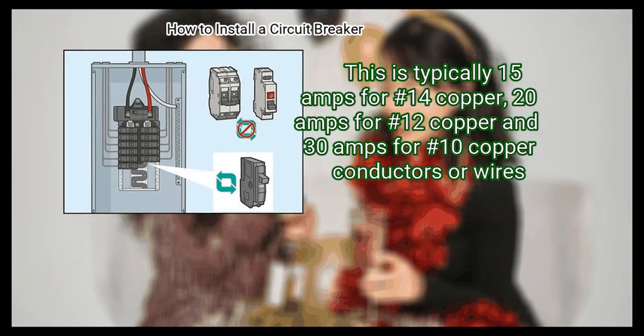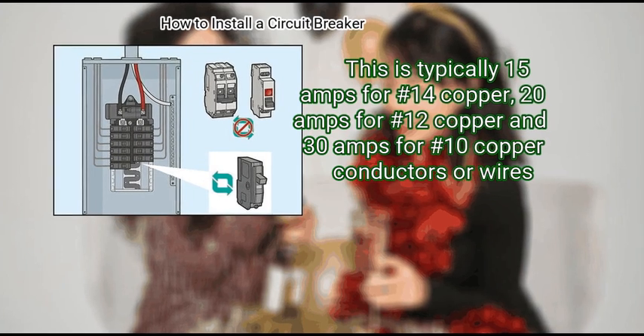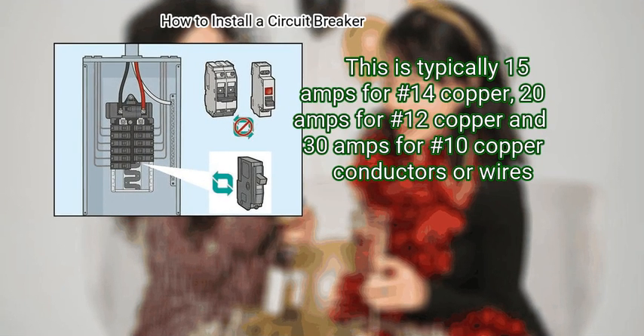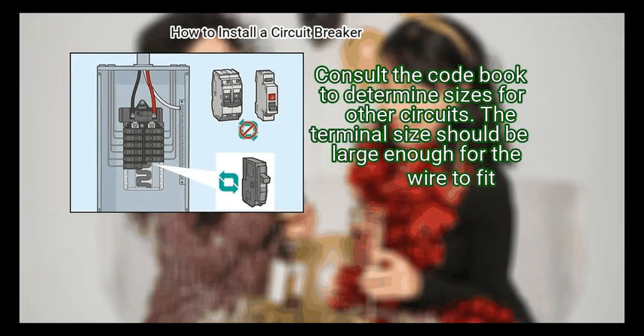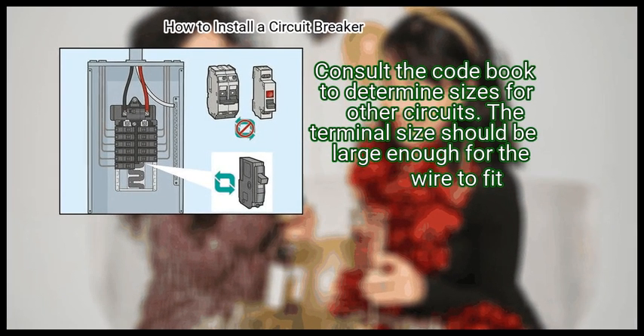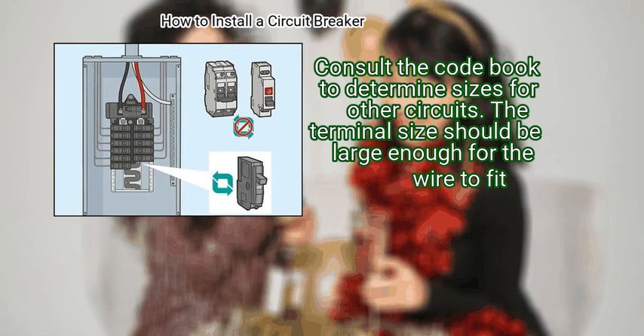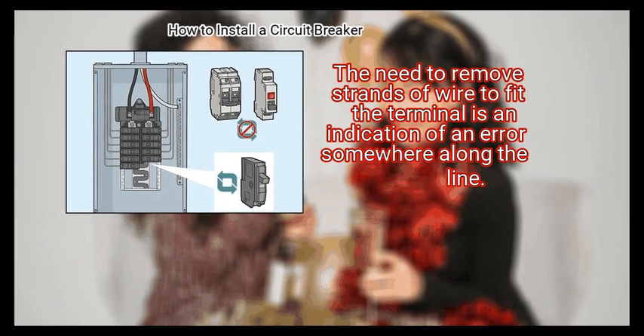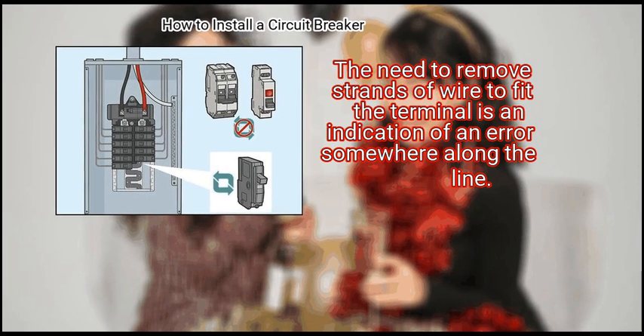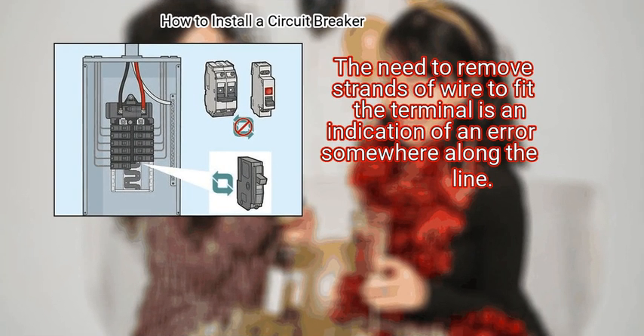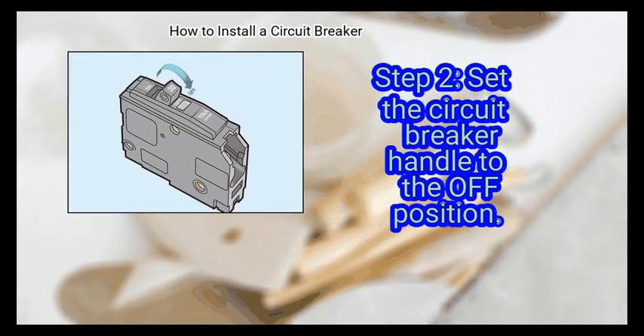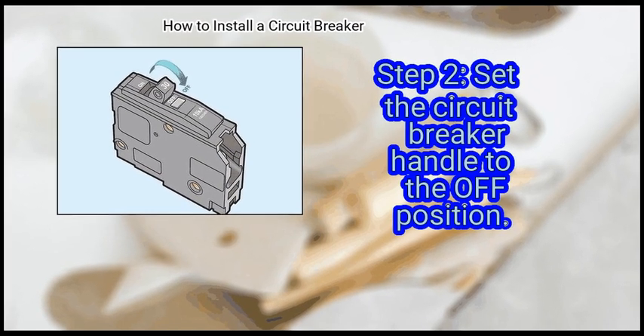This is typically 15 amps for number 14 copper, 20 amps for number 12 copper and 30 amps for number 10 copper conductors or wires. Consult the code book to determine sizes for other circuits. The terminal size should be large enough for the wire to fit. The need to remove strands of wire to fit the terminal is an indication of an error somewhere along the line. Step 2. Set the circuit breaker handle to the off position.